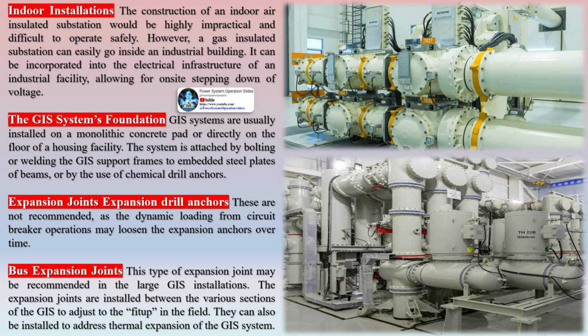GIS systems are usually installed on a monolithic concrete pad or directly on the floor of a housing facility. The system is attached by bolting or welding the GIS support frames to embedded steel plates or beams, or by the use of chemical drill anchors. Expansion anchors are not recommended, as the dynamic loading from circuit breaker operations may loosen them over time.